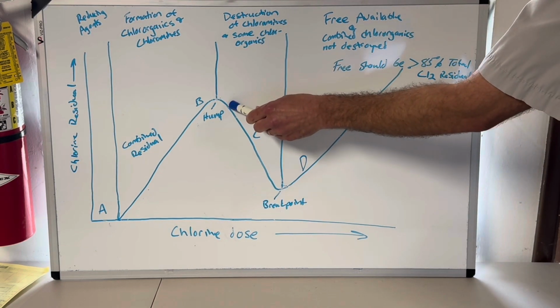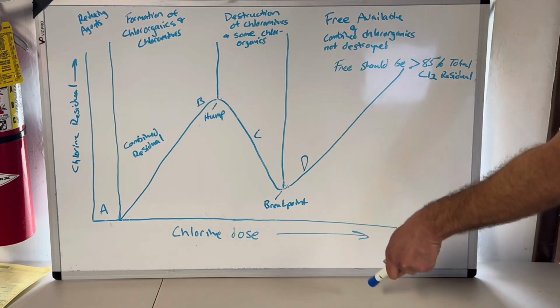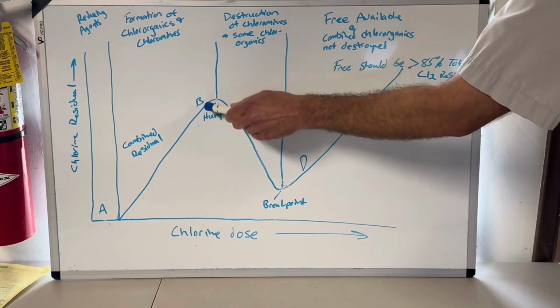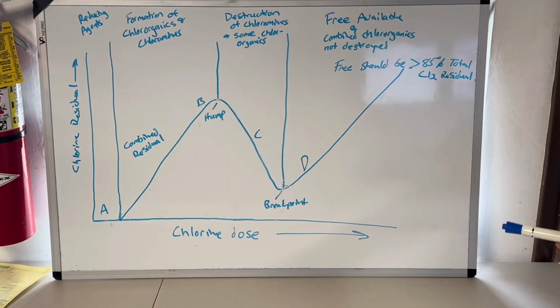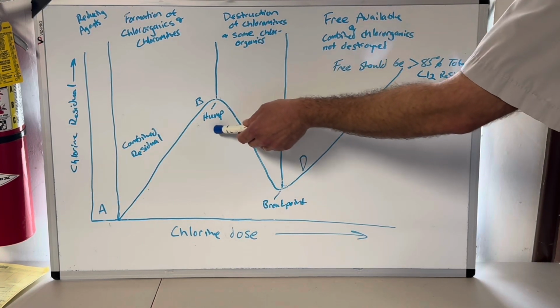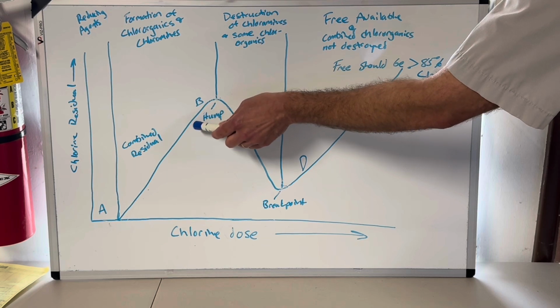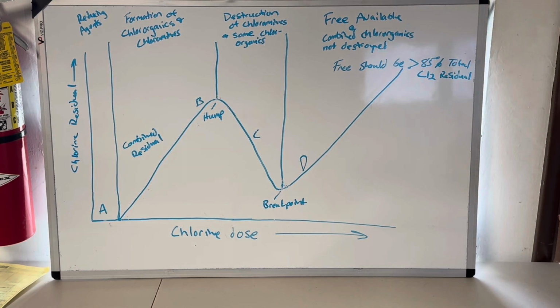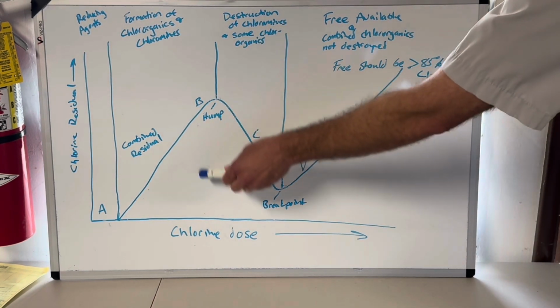Maybe I'm actually here and maybe ammonia dropped. That's why I actually like to run a 3-to-1. If there's a drop in ammonia, I don't have a lot of control over that. I don't have online analyzers here to tell me what my ammonia is. I don't even know if that's a thing to have an online ammonia analyzer for wastewater. I'm sure there is. They got analyzers for everything. But I'm doing grab tests when things like this are happening, and I'm analyzing what's going on.